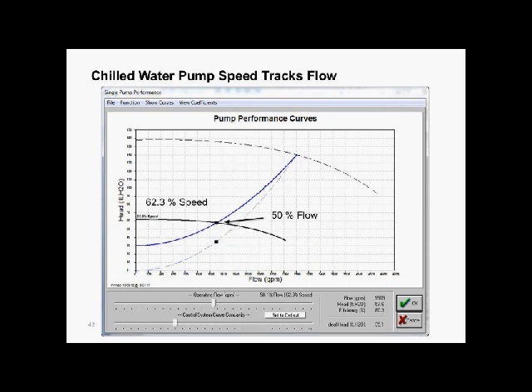I have a set point, some pressure sensor out near the end of the system that's got to be higher than whatever the last coil and the last valve requires. So I've got to set it up to some number. I've picked 30 feet here. Now you'll notice that I'm not operating here anymore. I've had to increase speed to be up here to cross that curve. Now I'm at 62% speed to do 50% flow.